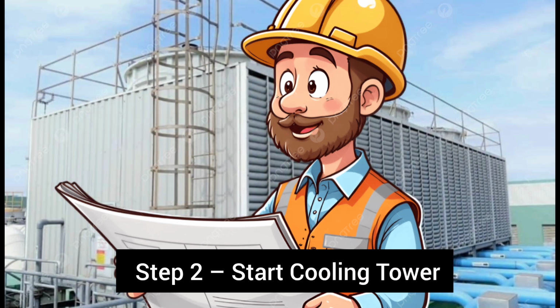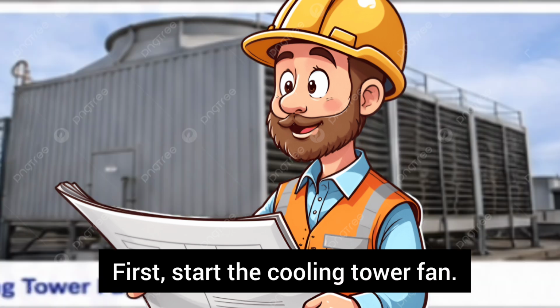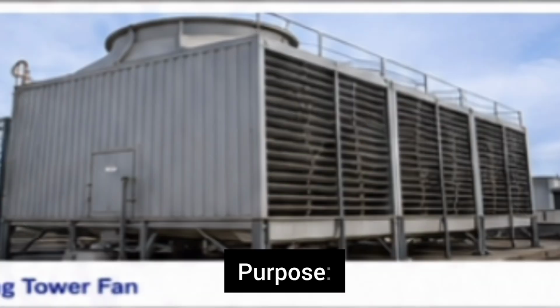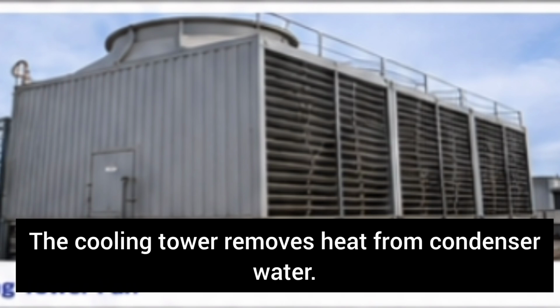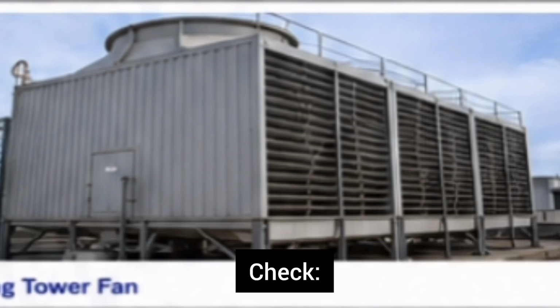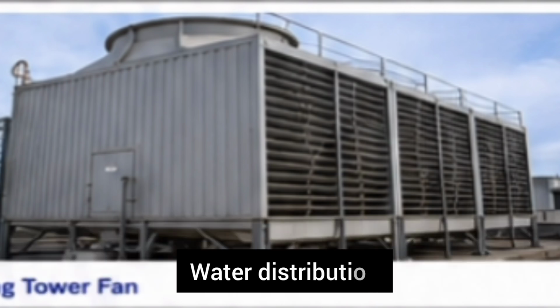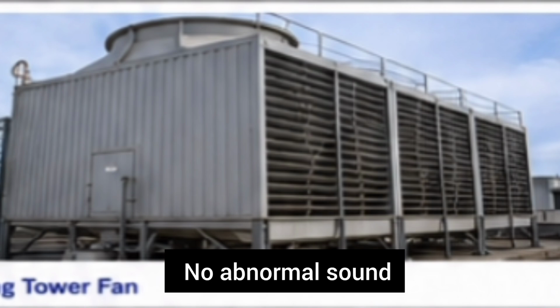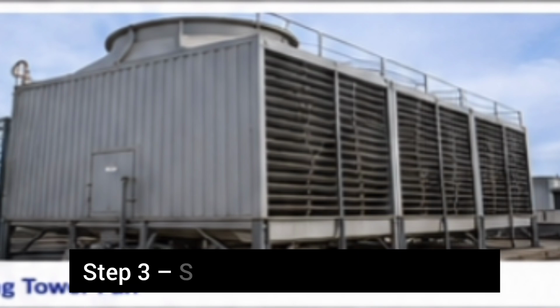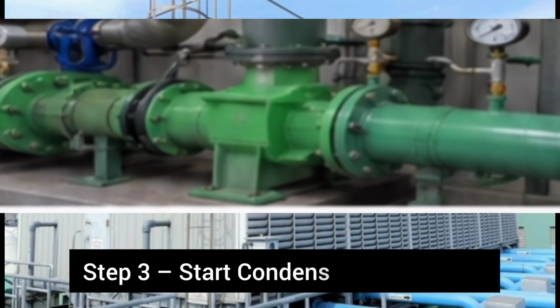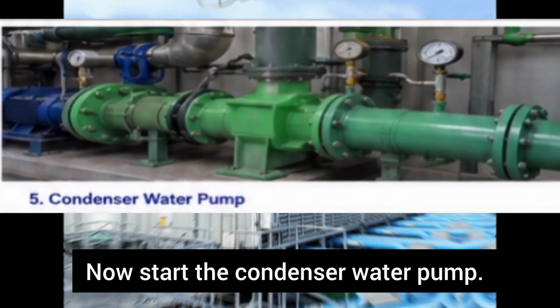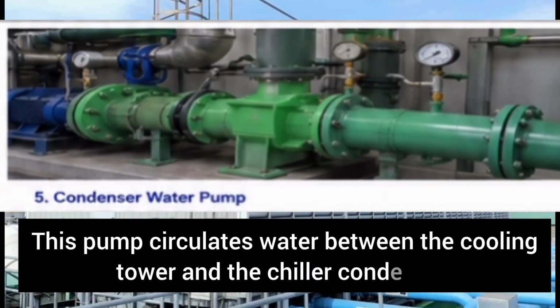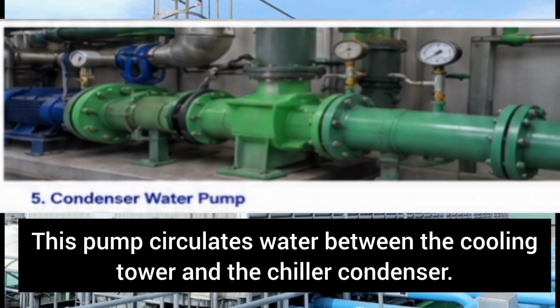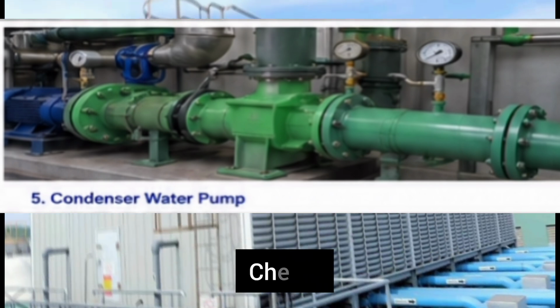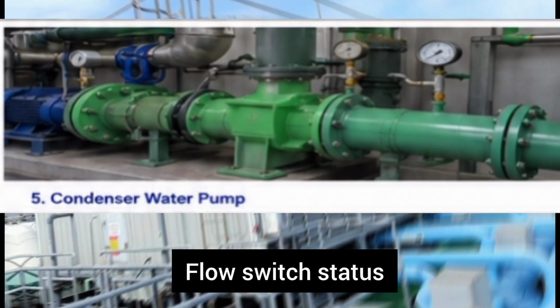Step 2. Start cooling tower. First, start the cooling tower fan. Purpose: the cooling tower removes heat from condenser water. Check fan rotation, water distribution, no abnormal sound, basin level. Step 3. Start condenser water pump. Now start the condenser water pump. This pump circulates water between the cooling tower and the chiller condenser. Check pump pressure, flow switch status, no leakage, motor current.